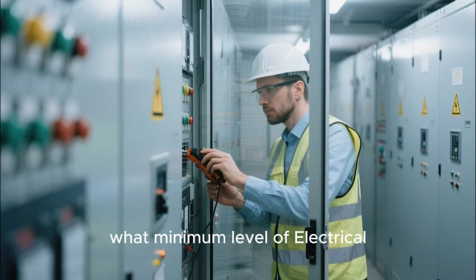When opening the screen door to check the operating equipment, what minimum level of electrical safety must the inspector have? Answer: the person must have electrical safety level 3 or higher.